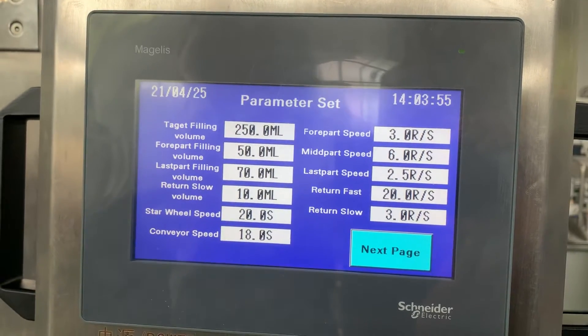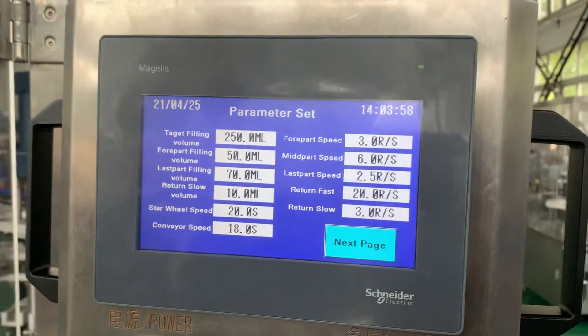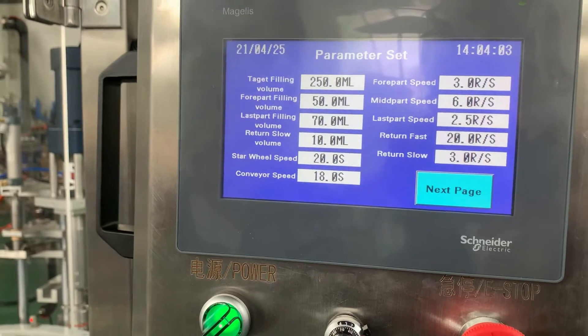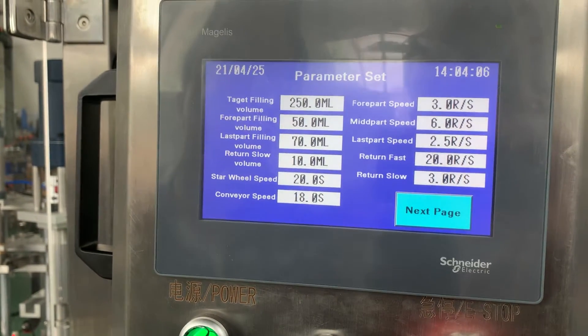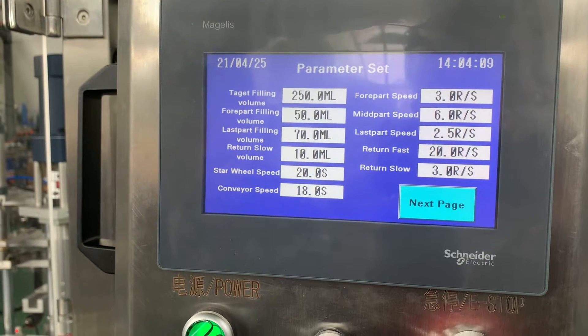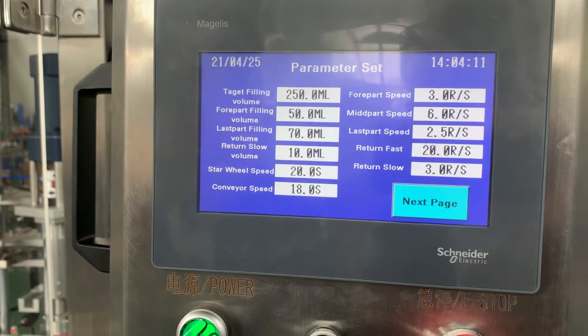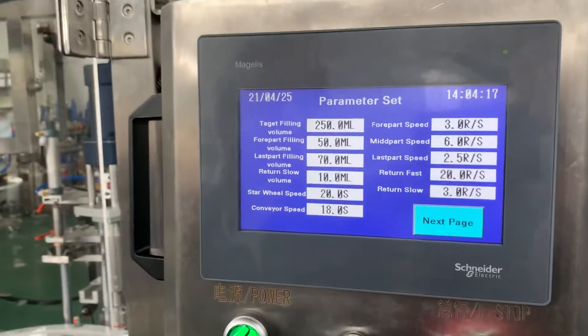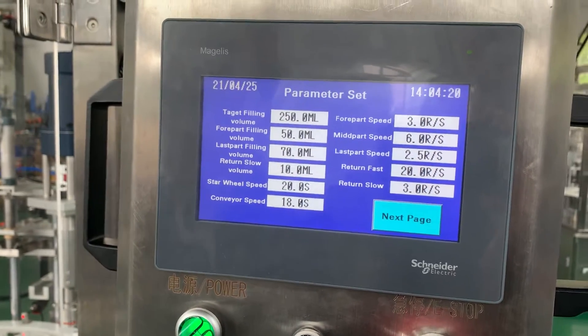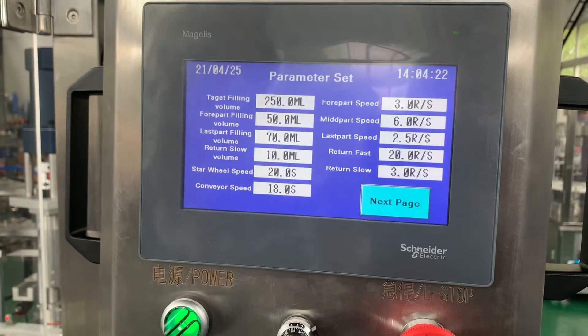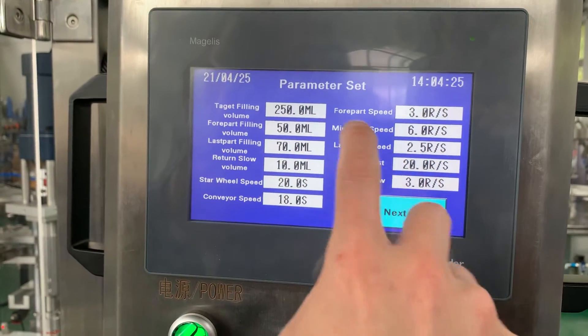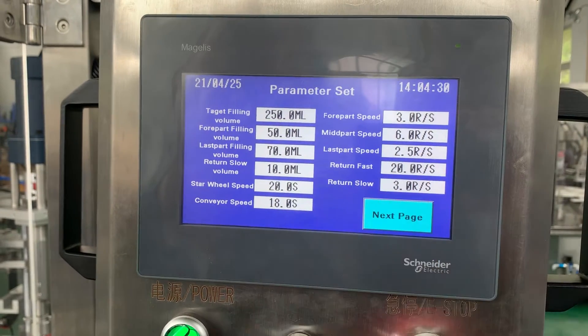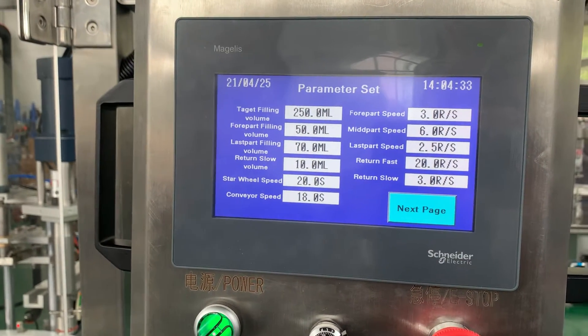The machine has three different speed phases during filling. The first part filling volume is 50 ml, filled at low speed. The last part filling volume is 70 ml, also filled at low speed. The first part speed is 3 rounds per second and the last part speed is 2.5 rounds per second — this is to avoid foam.